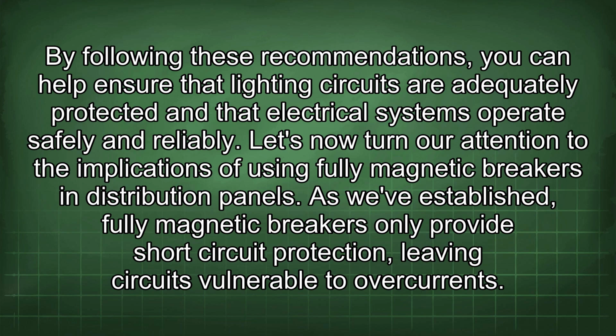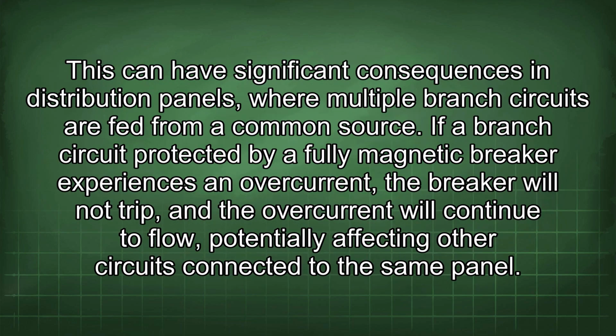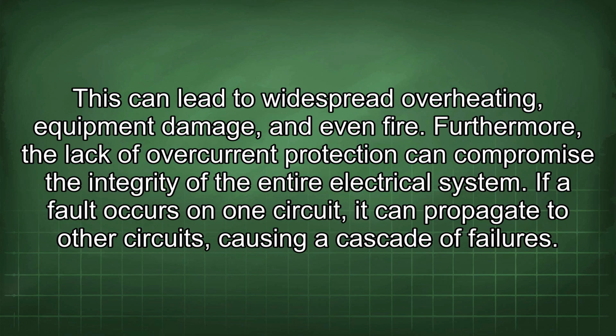Let's now turn our attention to the implications of using fully magnetic breakers in distribution panels. As we've established, fully magnetic breakers only provide short-circuit protection, leaving circuits vulnerable to overcurrents. This can have significant consequences in distribution panels, where multiple branch circuits are fed from a common source. If a branch circuit protected by a fully magnetic breaker experiences an overcurrent, the breaker will not trip, and the overcurrent will continue to flow, potentially affecting other circuits connected to the same panel. This can lead to widespread overheating, equipment damage, and even fire.